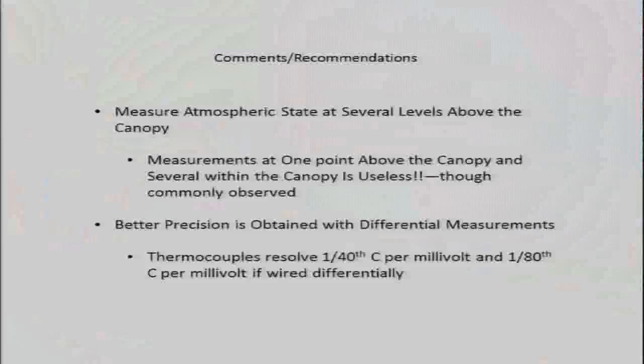If you're using thermocouples, for example, the resolution of thermocouples wired in differential mode is much better than individually wired ones. We can actually resolve gradients on the order of an 80th of a degree Celsius per millivolt. So thinking about how you wire and implement the sensors is quite critical in this type of work.